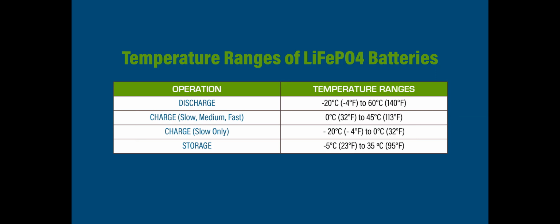When you're charging lithium batteries, you can charge them slow, medium, or fast in that wide moderate temperature range from freezing to 113 degrees Fahrenheit, no concerns. When you get into the cold, you want to only charge our batteries slow. There's a chart a little later where we'll look at what that means, but if you don't have cold temperature applications, you don't have to worry about that.